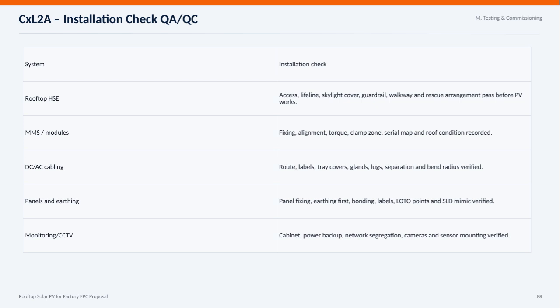Panels and earthing are thoroughly checked for secure fixing, proper earthing and bonding, clear labeling, lockout-tagout points, and accurate single-line diagram mimic. Finally, the monitoring and CCTV aspects include verifying the cabinet setup, power backup, network segregation, and the correct mounting of cameras and sensors to ensure reliable system oversight. These checks are critical to guarantee both safety and performance before commissioning the solar PV system.